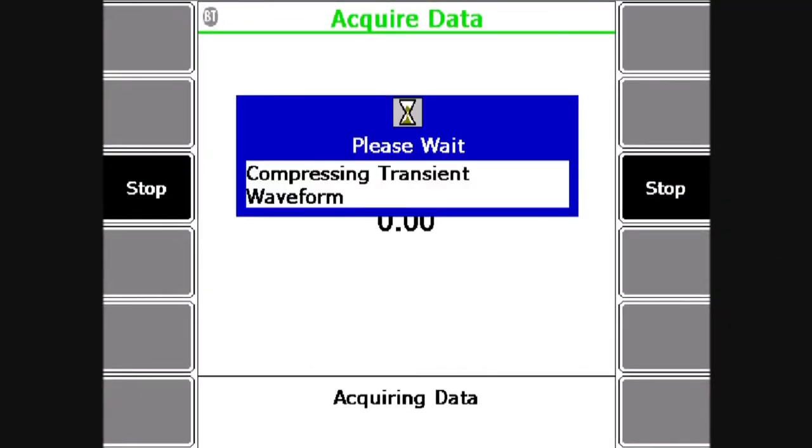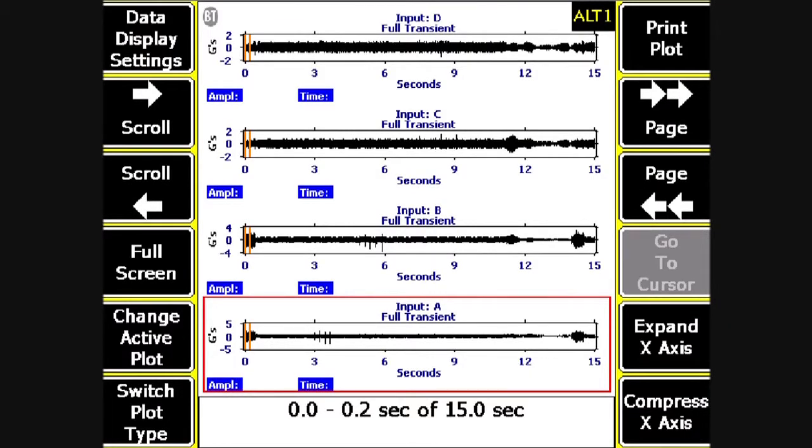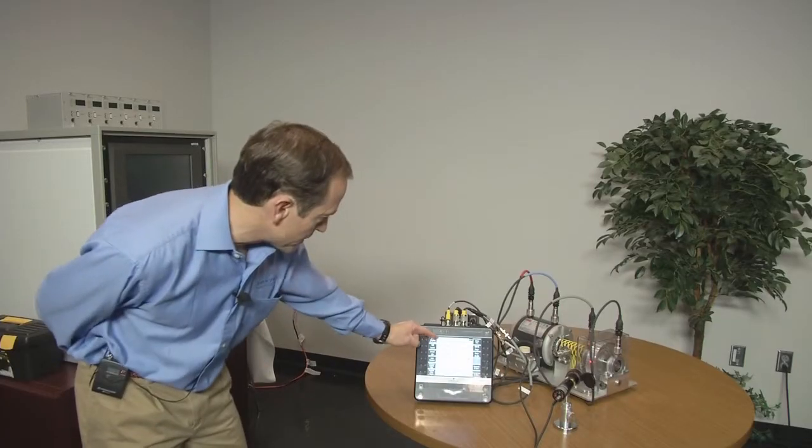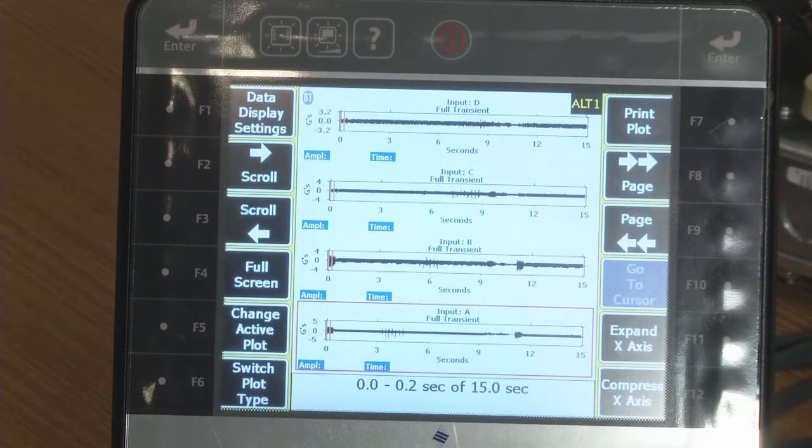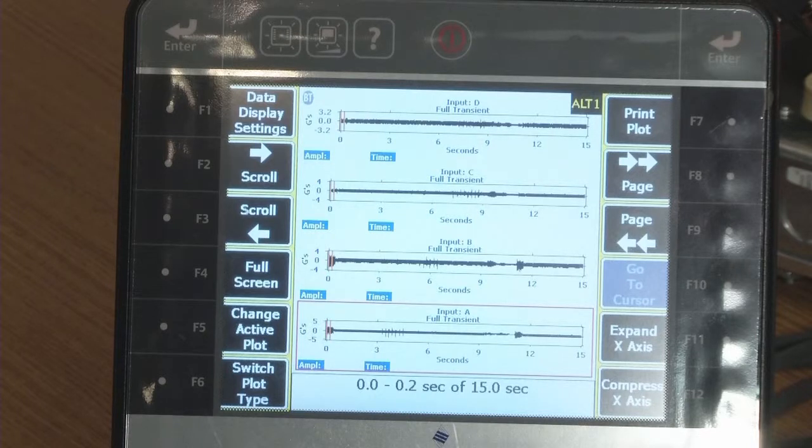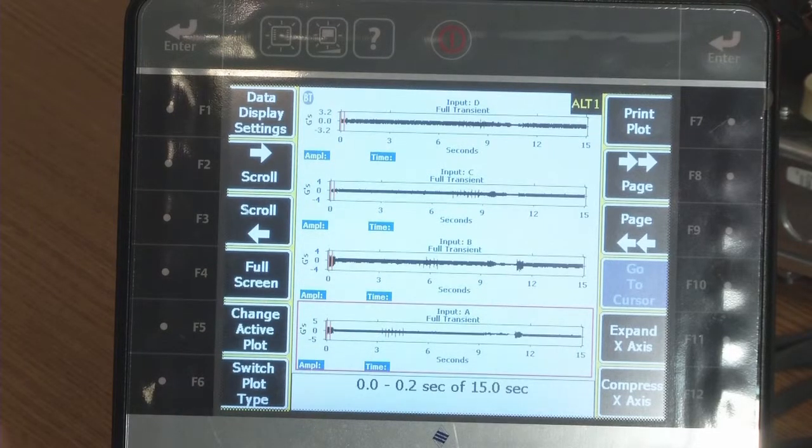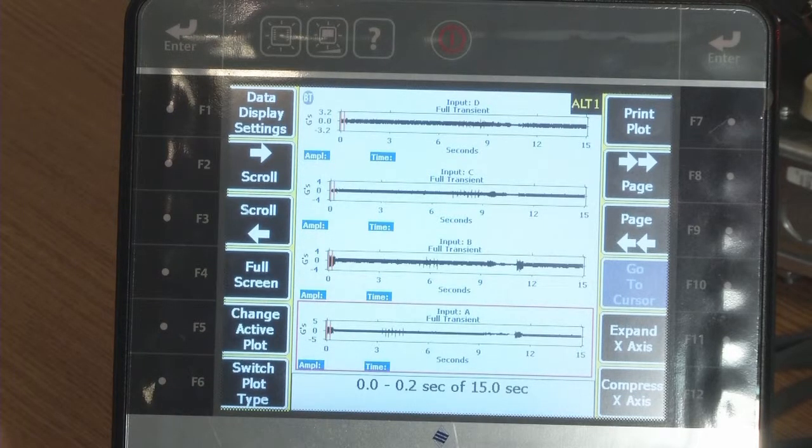Over that 15 seconds, we've just collected data on all four channels simultaneously, and the result is I can see all 15 seconds for each waveform. On the transient channel A, where these high peaks are, this is exactly where the impacts were. You can see where the amplitude goes to zero, and that is where we turned the machine off and then started the machine back up again.